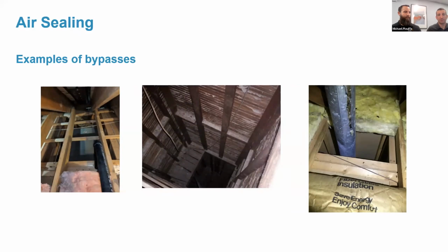Because you don't want to seal a building up too much, because that can adversely impact indoor air quality for the occupants. So part of a weatherization project, typically we would do a blower door test, which prior to installing any weatherization measures, would measure the air leakage rate of the building, and then that could be compared to ASHRAE required air exchange levels, particular to that facility type. So different types of facilities have different required ventilation rates. So, a school or a restaurant or a number of different types of facilities might require different levels of mechanical ventilation.